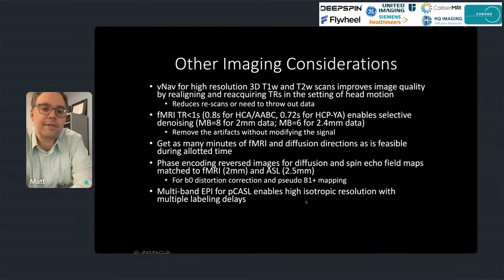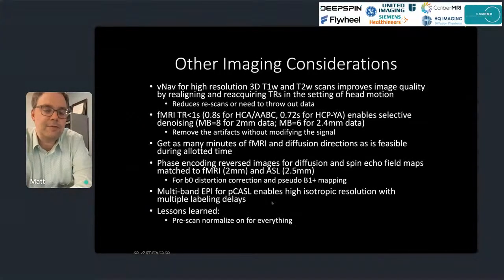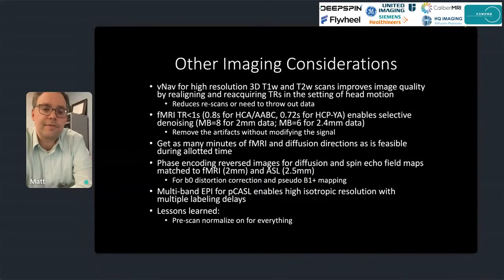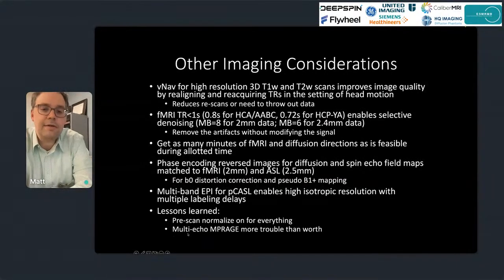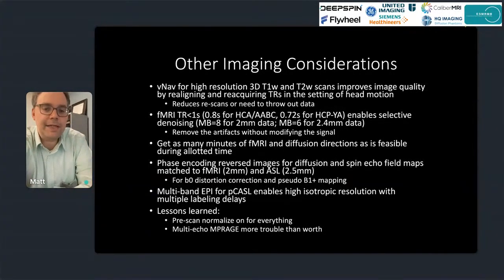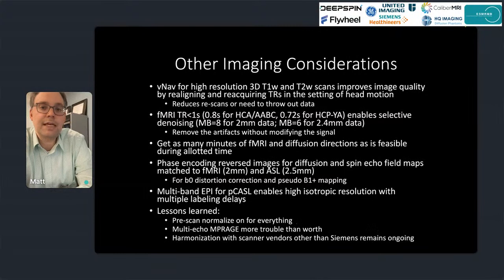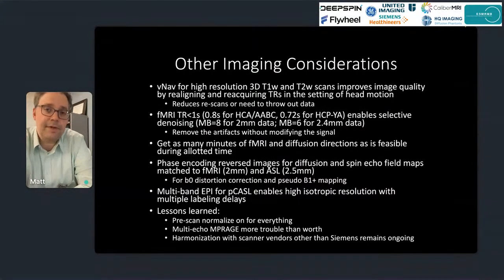Some lessons learned in HCP: it really helps to have pre-scan normalization on for all your scans — T1s, T2s, fMRI, diffusion, even spin echo field maps — as it makes downstream artifact correction a little easier. We used multi-echo MPRAGE for the lifespan studies, which ended up being more trouble than it was worth; there were artifacts in those data that led to not being able to use them to their fullest potential. HCP has been very Siemens-centric — Siemens was ahead of the curve with MR technology, but it's been over a decade since HCP started and the other vendors are catching up, though good harmonization is still an ongoing process.